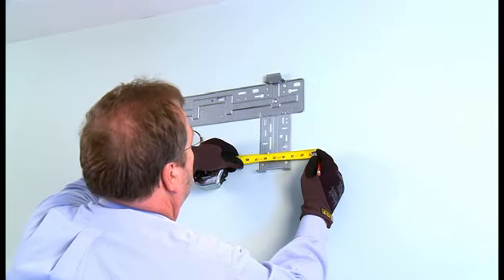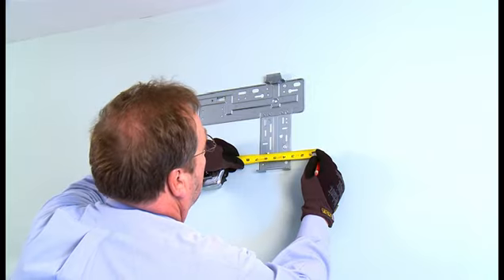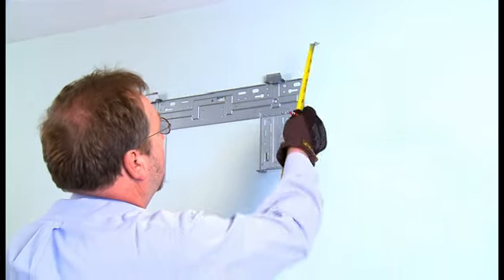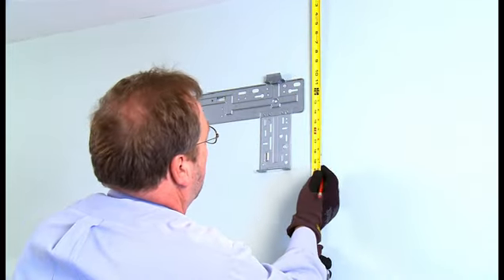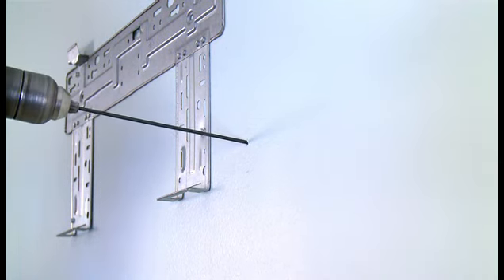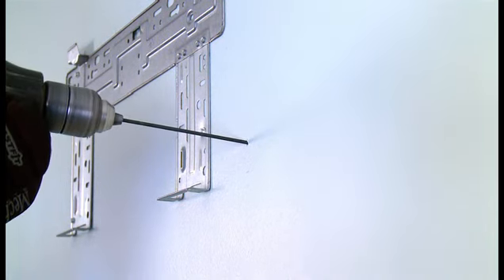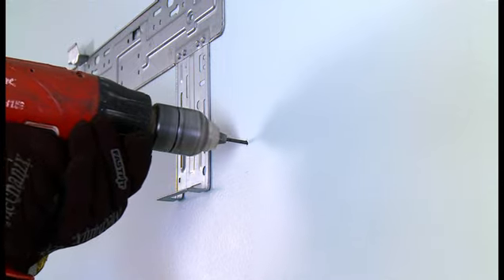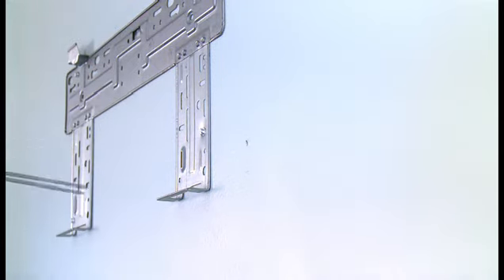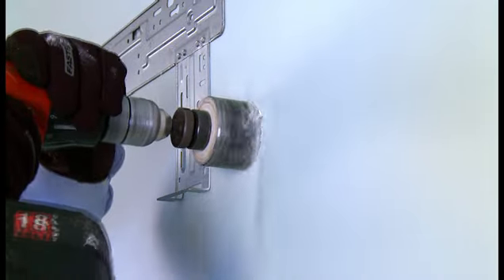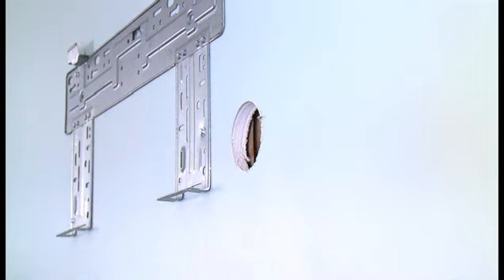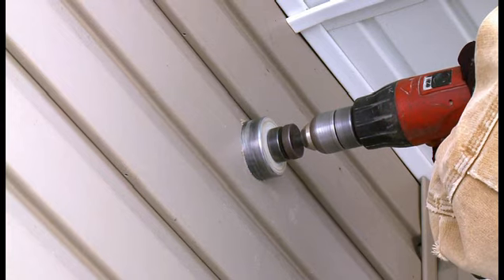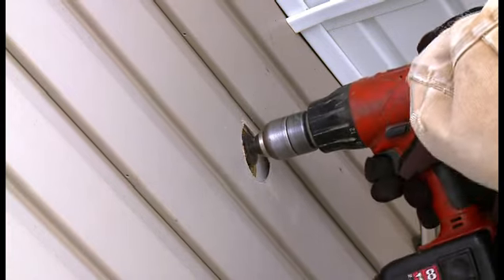In these next steps, we'll create the hole that will accommodate the drain hose and the line set, comprised of the refrigerant connective pipes. Referring to the instruction manual for your particular model, determine where to drill the hole that will accommodate the drain hose and the line set. Next, using a core drill and bit, drill the hole in a downward direction of 30 degrees. This facilitates drainage to the building's exterior. Complete the hole by drilling through from the structure's exterior wall.